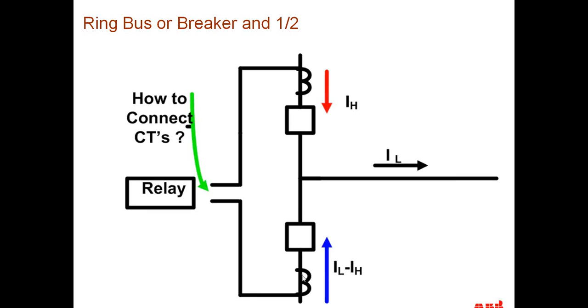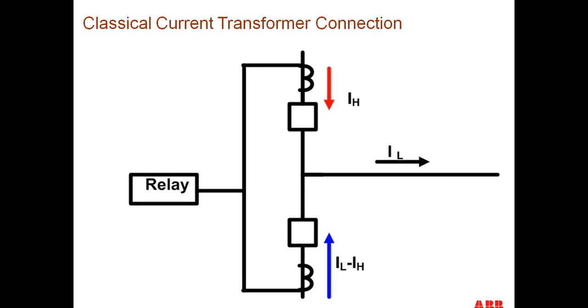When we get into a ring bus or breaker and a half scheme, now we have to worry about two different breaker CTs that are going to be fed into the relay, and how to connect these CTs into the relay is the question, because we have the current through one breaker plus the current from the other breaker adding together to come out with what our line current is. The conventional approach was to use a single input on the IED and connect these two current transformers in parallel and bring them into the relay. As you see right here, we're connecting both CTs external to the relay in parallel and bringing them into one relay input.